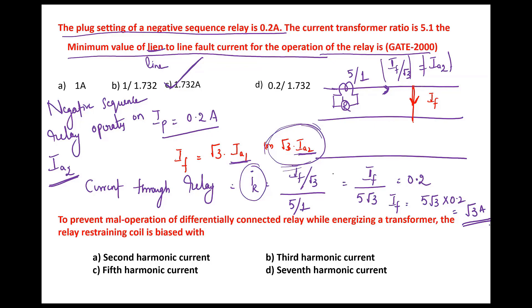To prevent the mal-operation of the differentially connected relay while energizing the transformer, the relay restraining coil is biased with the second harmonic of the current. We pass the second harmonic current through the restraining coil to provide additional restraining force, which prevents the operation of the differential relay during charging of the transformer. This component is very large in magnetic inrush currents — from 30 to 70 percent.